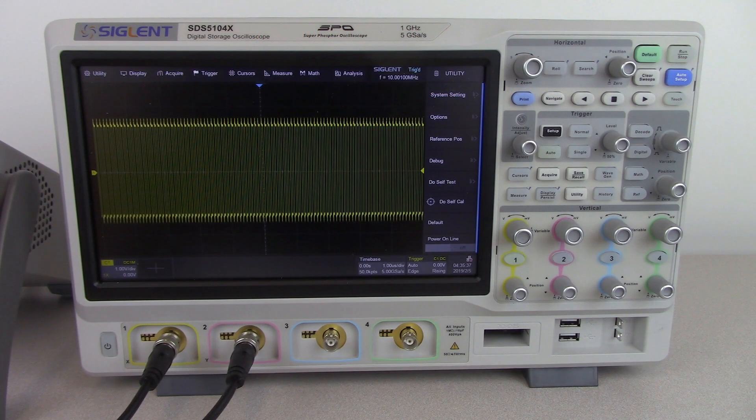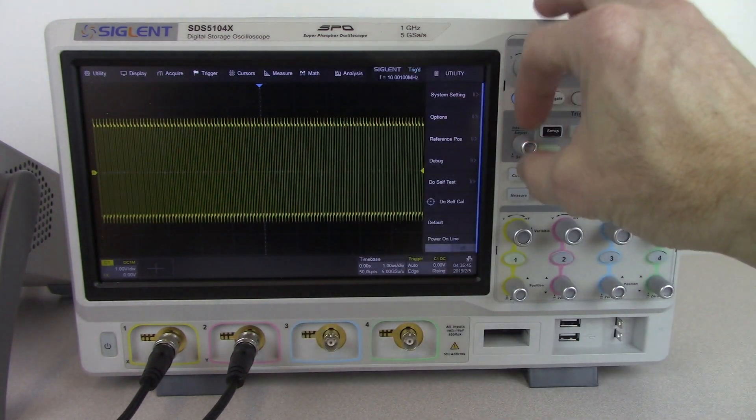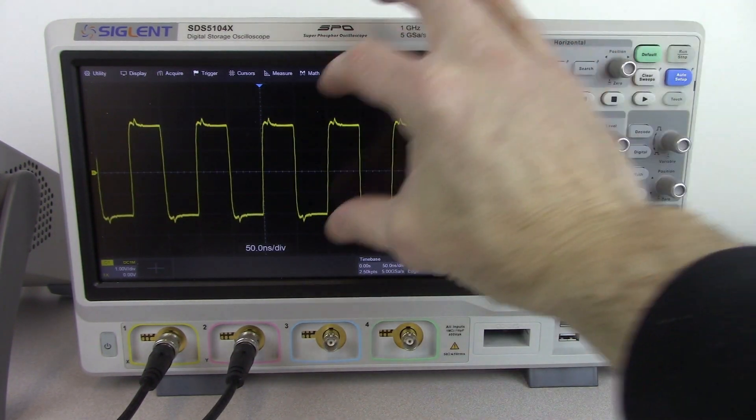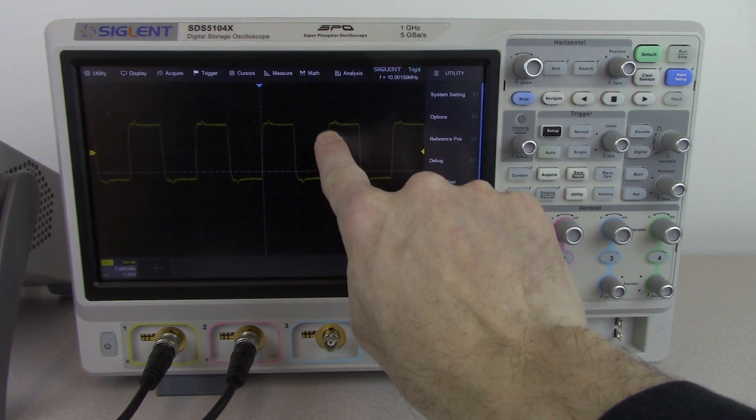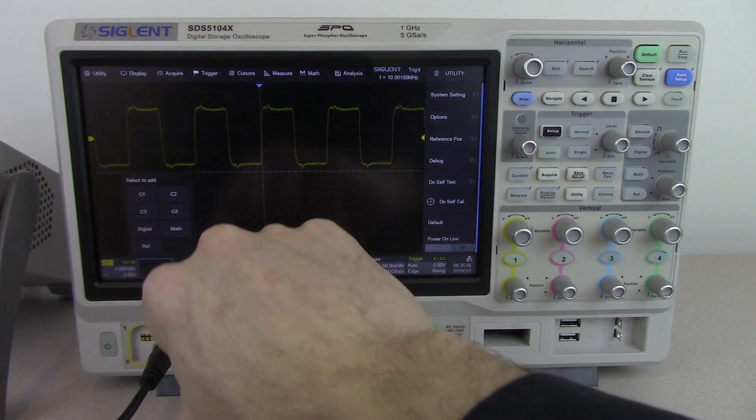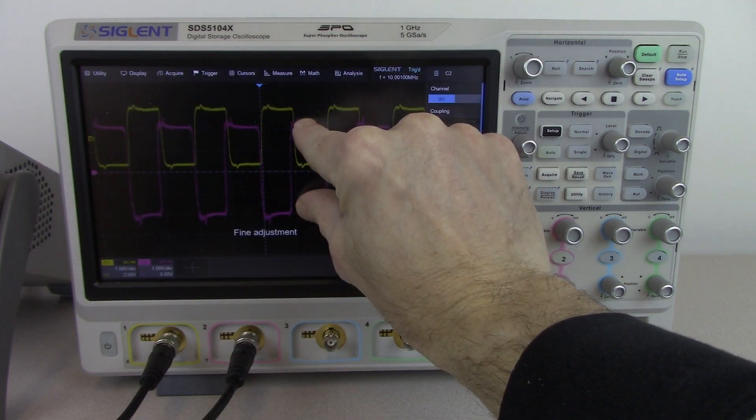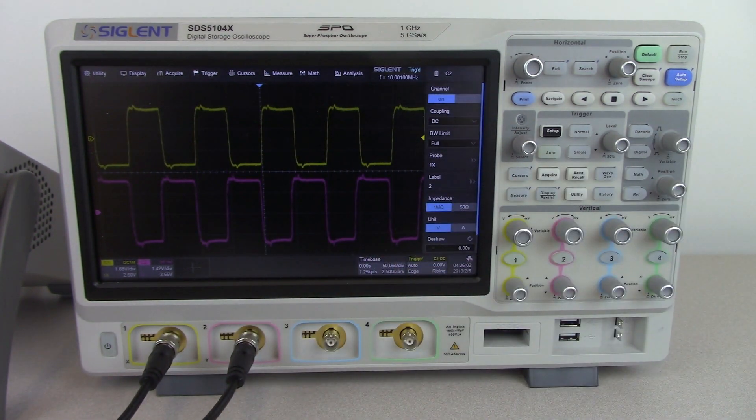I would like to talk a little bit more about the cycle-to-cycle jitter and other measurement statistics that we have on the new 5000 series. In this case, I have a square wave on channel 1 being generated by one of our generators. I'm also going to add channel 2, which is slightly more jittery using a different circuit or technique with our waveform generator.